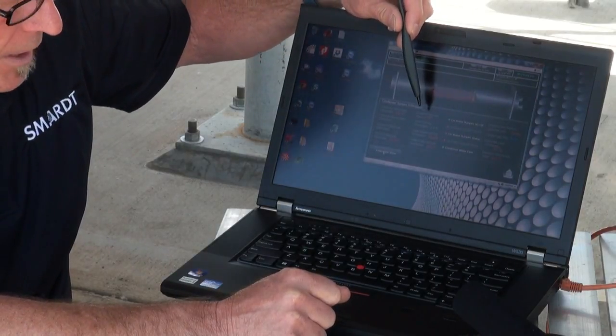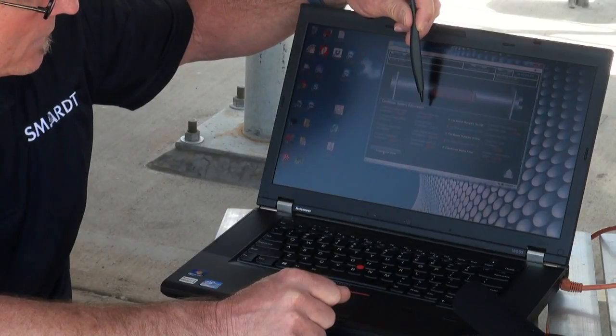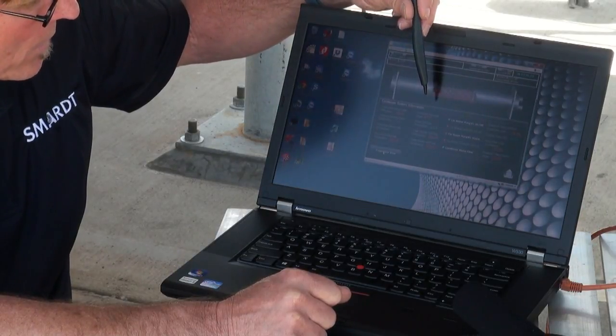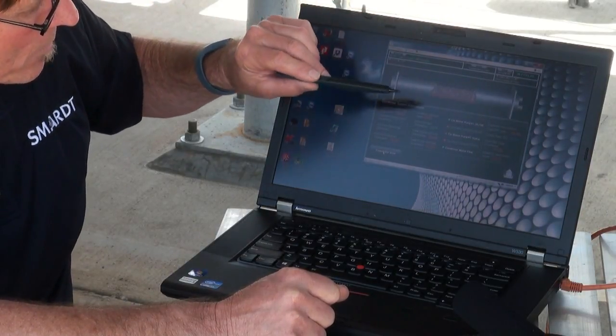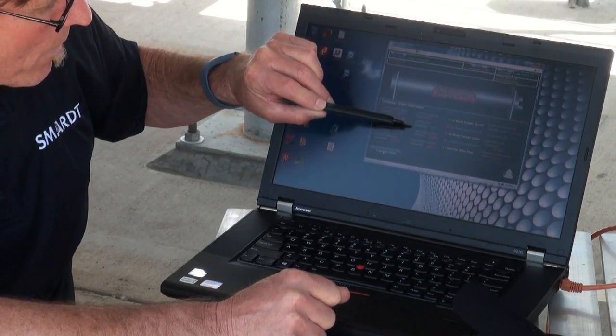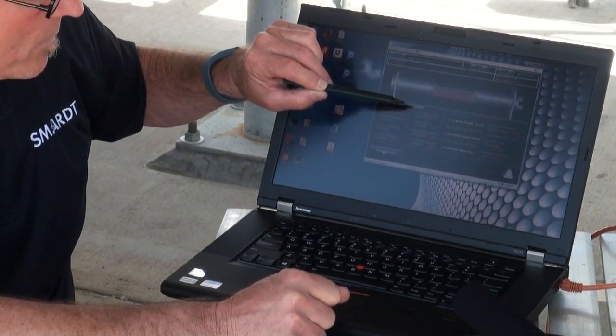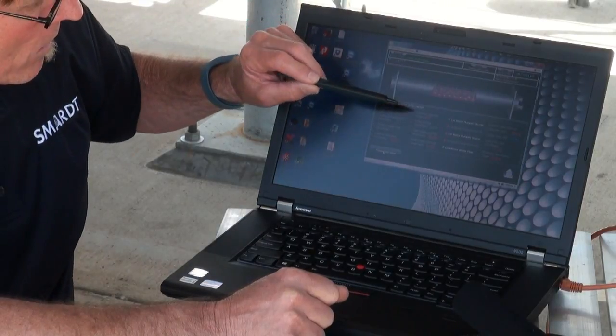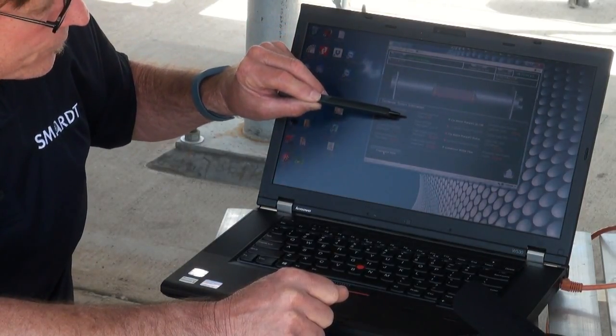than that. If you're getting higher approach temperatures than that, then there could be some fouling issues or something going on with your condenser. So it might be time for service. Something you want to eyeball, something you want to log when you do your chiller logs.